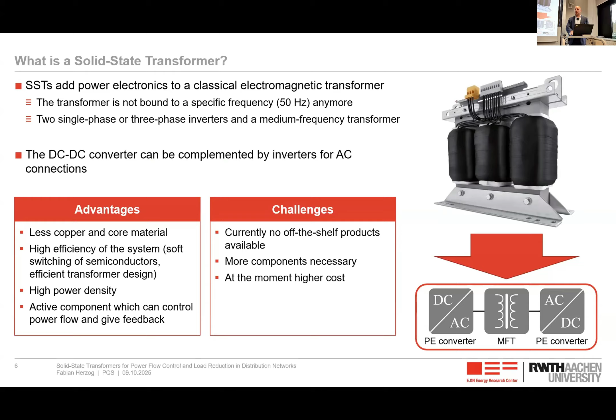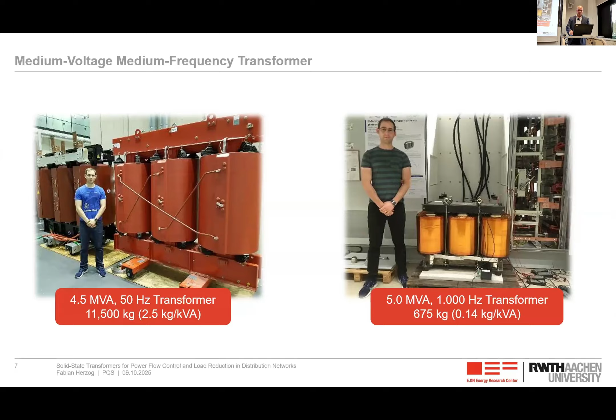But that may change in the future because, as we can see, there is a lot of material in the 50 Hertz transformers. To show you this, I have a picture here from a former chief engineer of our institute. On the left side, a 4.5 megavolt ampere transformer from a wind turbine, which weighs 11.5 tons. And on the right side, the medium frequency transformer in our test hall, which is 5 MVA, so slightly more than on the left side, also for medium voltage, so 5 kV to 5 kV. And here we only have a weight of 675 kilograms. We can see the density is much higher. We only need 140 grams per kVA for this medium frequency transformer, compared to 2.5 kilograms per kVA with the 50 Hertz transformer.